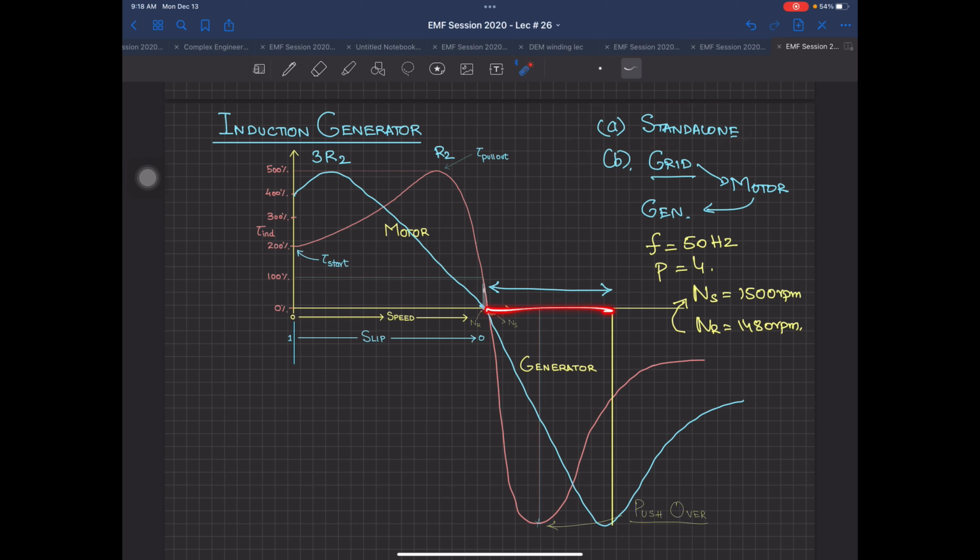So when you vary in this region, your bulbs, if they have been made for 50 hertz, go up to something like 60 hertz or 70 hertz, there will be a problem when the frequency changes. But when it is connected with the grid, the grid is so big that even a 1 kilowatt or a 5 kilowatt turbine will not alter the grid frequency that much. So the best case is that an induction machine is always connected with the grid.